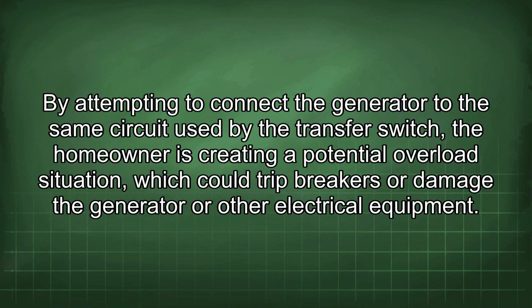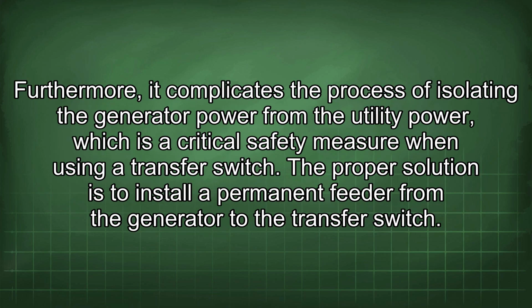By attempting to connect the generator to the same circuit used by the transfer switch, the homeowner is creating a potential overload situation which could trip breakers or damage the generator or other electrical equipment. Furthermore, it complicates the process of isolating the generator power from the utility power, which is a critical safety measure when using a transfer switch.